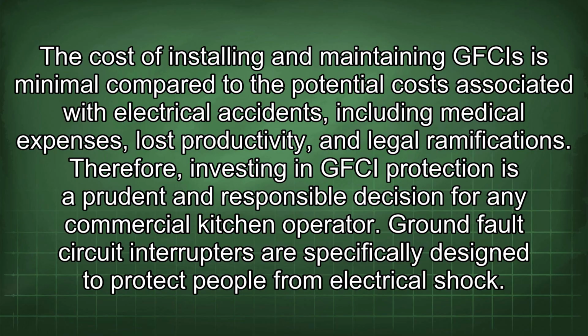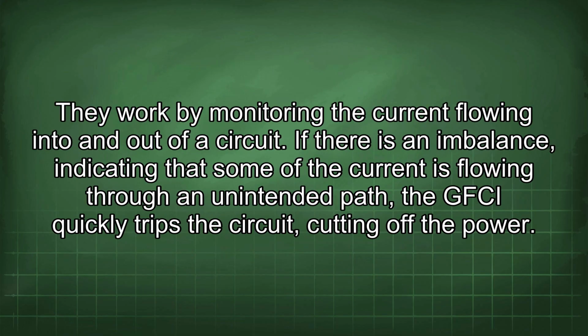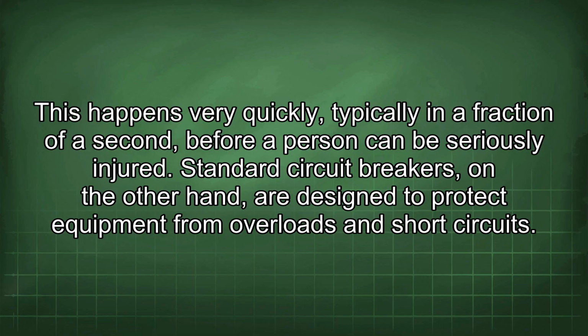Ground fault circuit interrupters are specifically designed to protect people from electrical shock. They work by monitoring the current flowing into and out of a circuit. If there is an imbalance, indicating that some of the current is flowing through an unintended path, the GFCI quickly trips the circuit, cutting off the power. This happens very quickly, typically in a fraction of a second, before a person can be seriously injured.